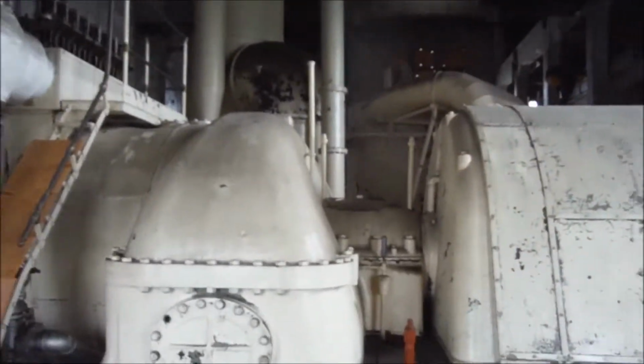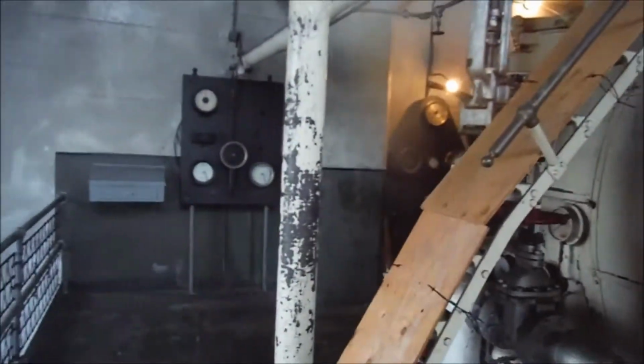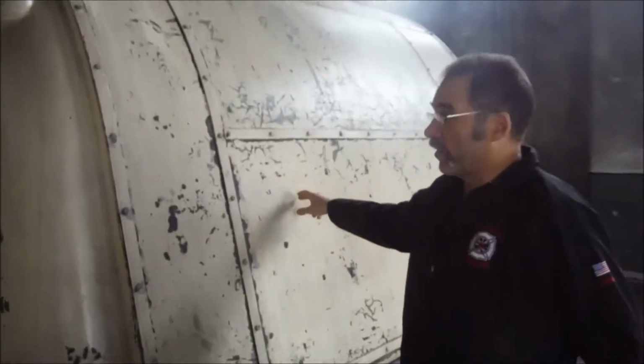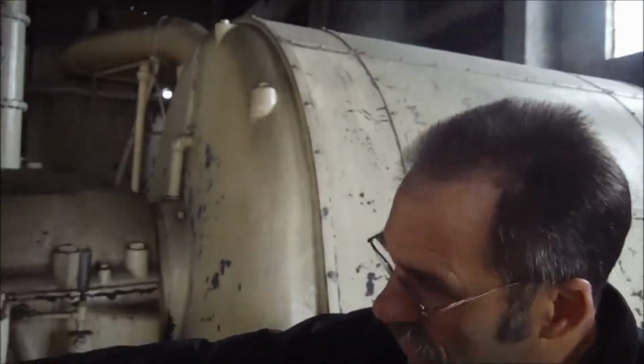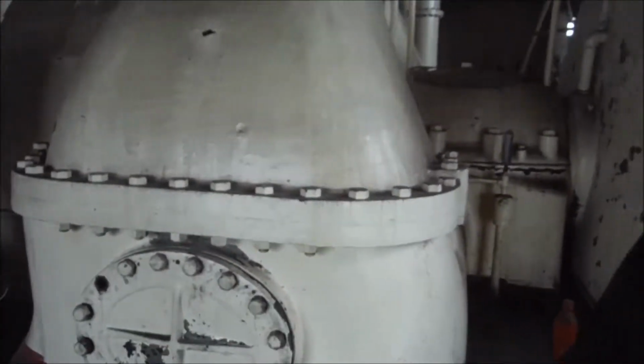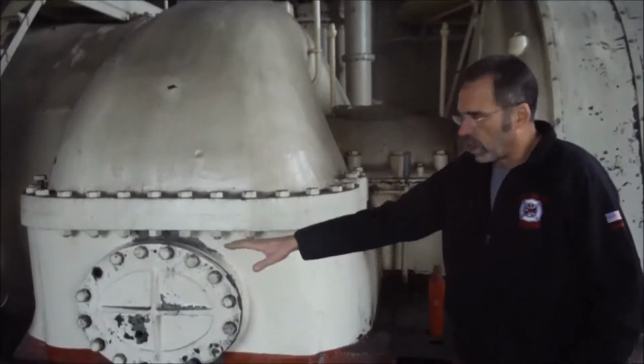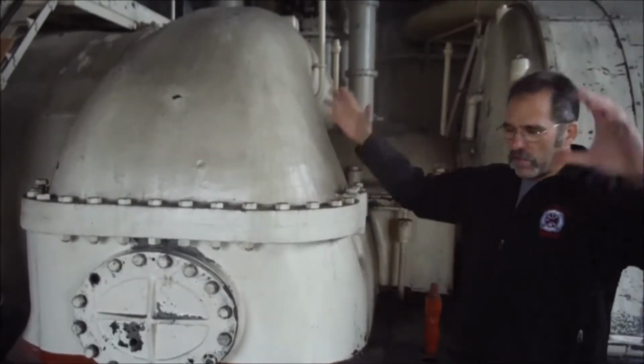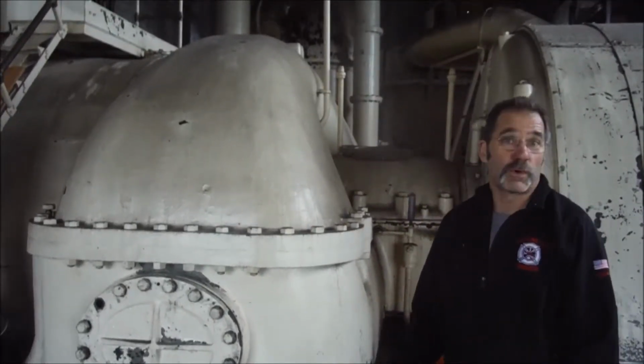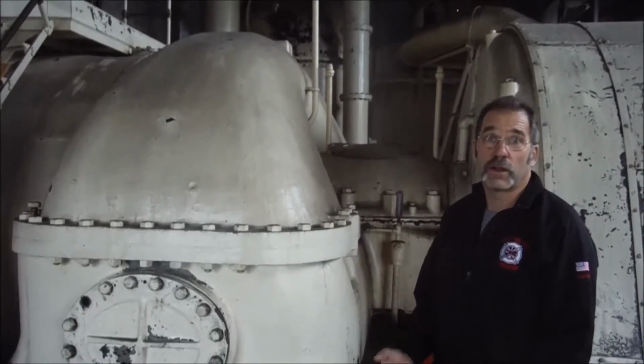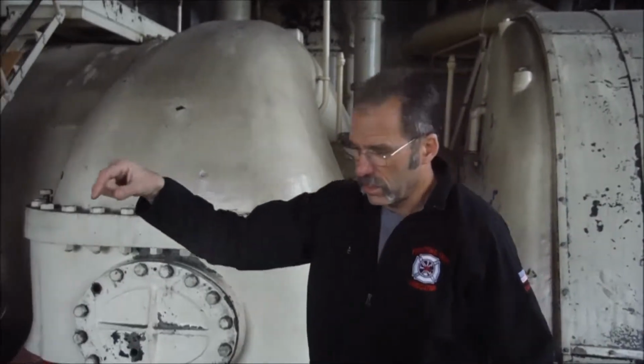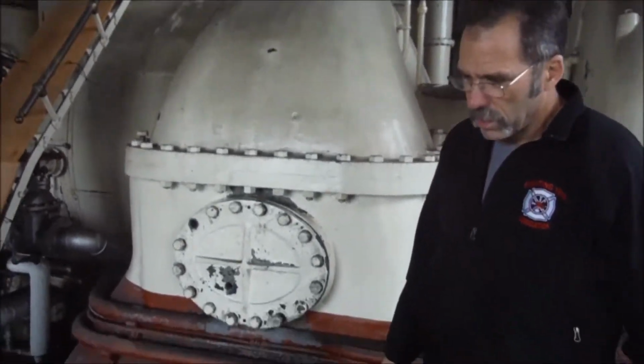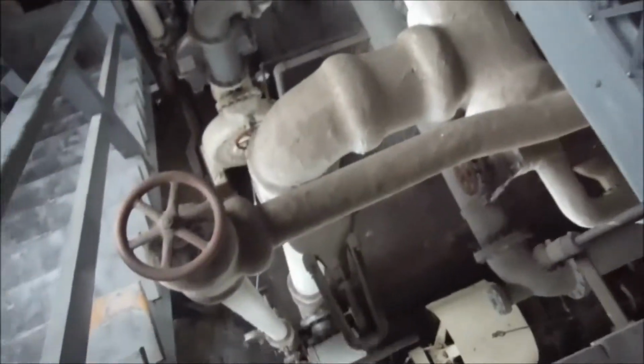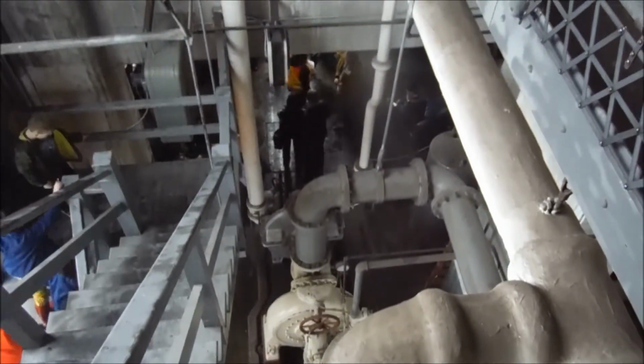This is so different in the daylight. So, obviously, this is the electrical generator here, horizontally mounted. This is the steam turbine, and then it exhausts downward, which they determined was more efficient, into that condenser that we saw below. So that condenser probably has horizontal tubes with river water flowing through them, and the steam comes out of the bottom of the turbine, hits the outside of those relatively cool tubes, condenses back to feed water, and goes back to the boiler room. I don't think they condensed their water and reused it. Maybe they just used raw river water. I think it was just the raw water system. But then that vacuum pump down there that we were looking at would have served the purpose of maintaining the vacuum in the condenser for the efficiency.